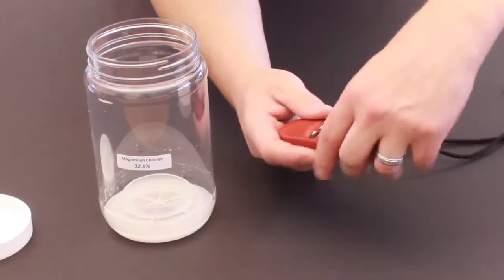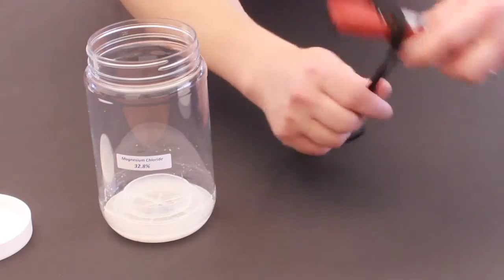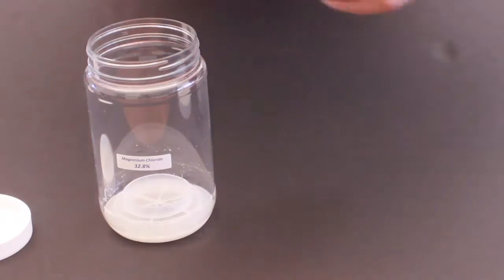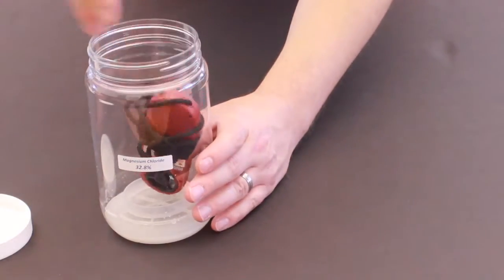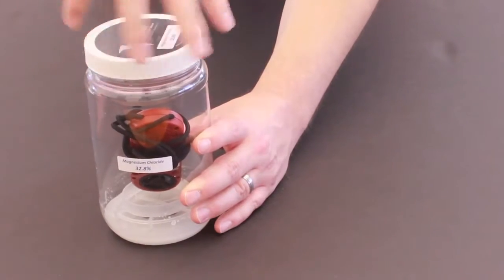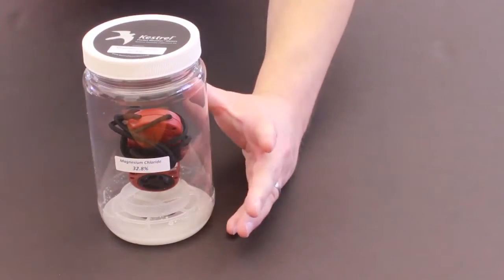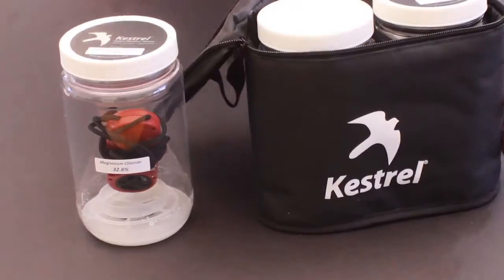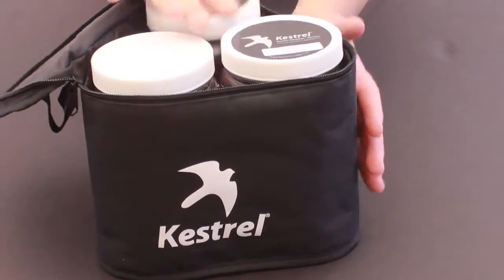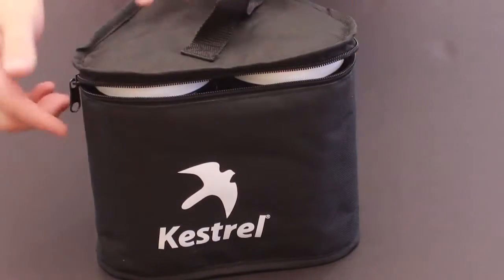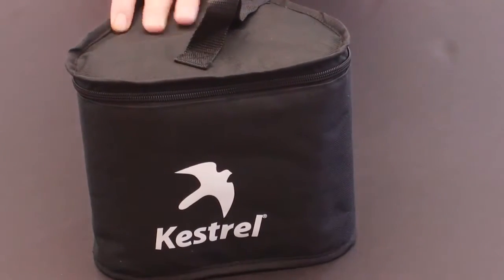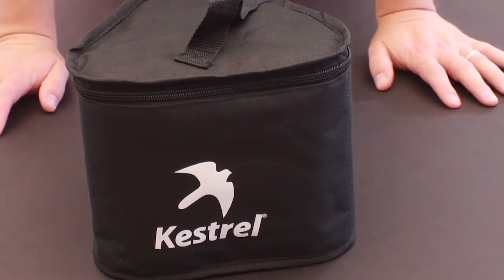We want to be careful to wrap the lanyard around so it doesn't touch the salts, and we're going to stick this upside down in this chamber and close the lid. Once the lid is closed, we want to put this back into our calibration kit and seal it up and set your timer for an hour.